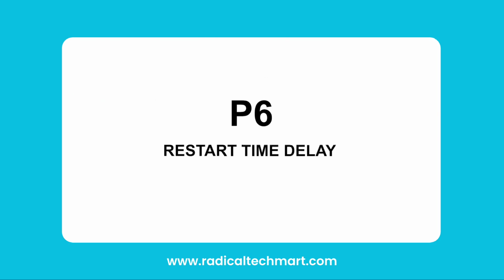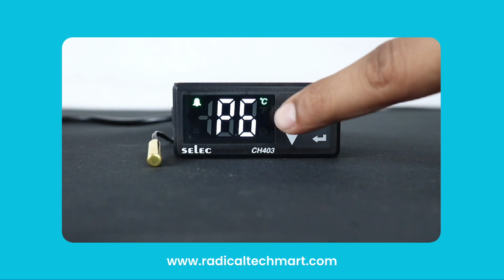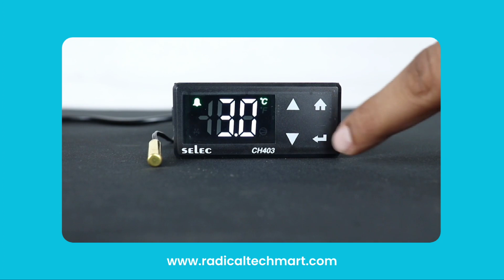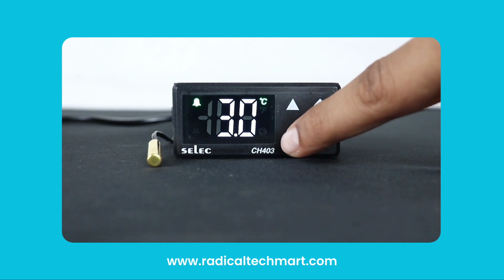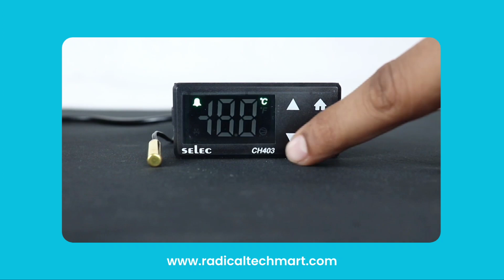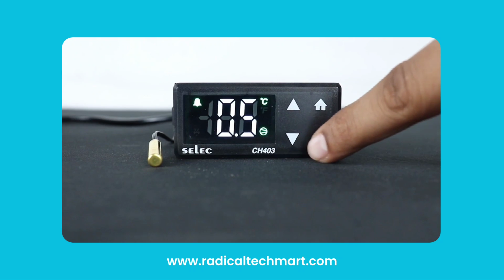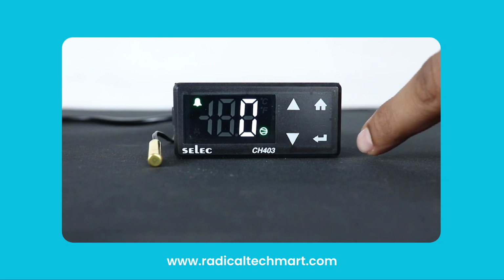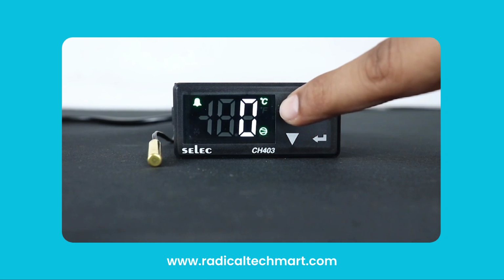P6 denotes the restart time delay. By setting this parameter, the user can set the time duration after which the relay turns on after a restart. It is used to prevent the compressor from restarting in a short period of time. Parameter P7 describes the defrost time function, which allows the user to change the time on which the relay or compressor turns off during defrosting.